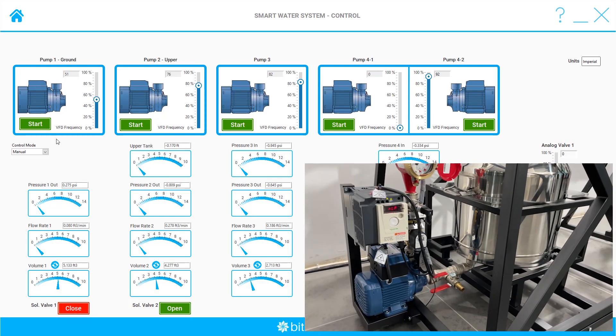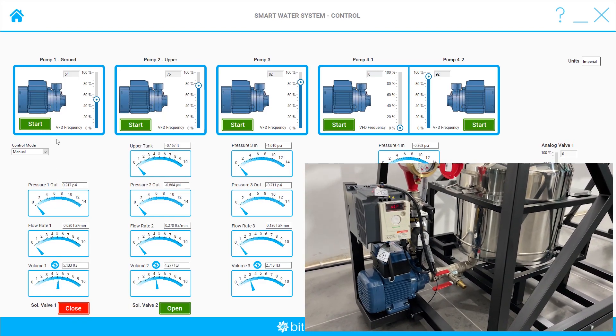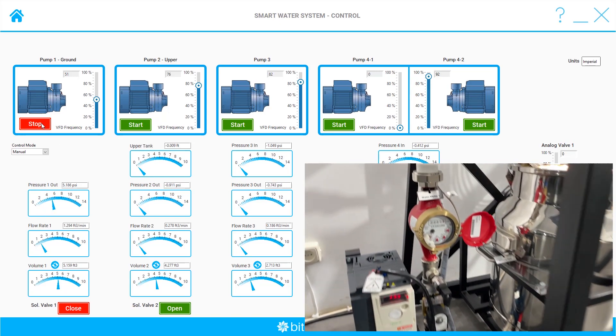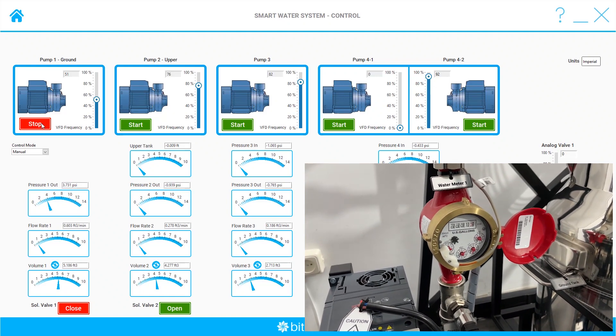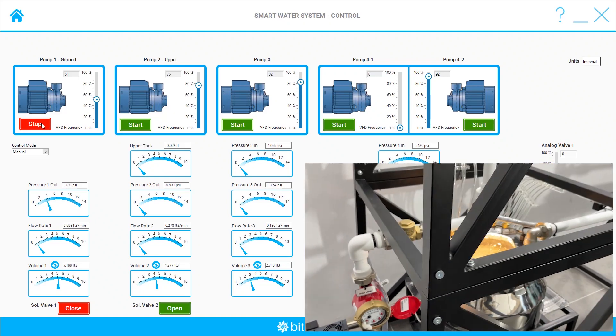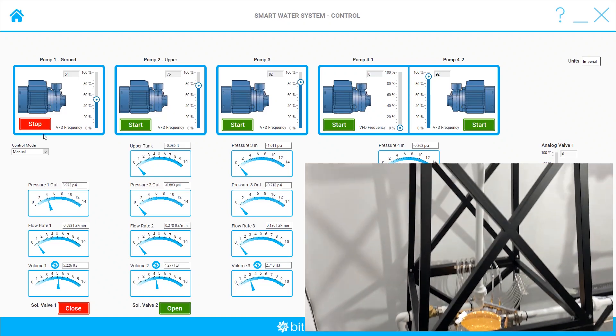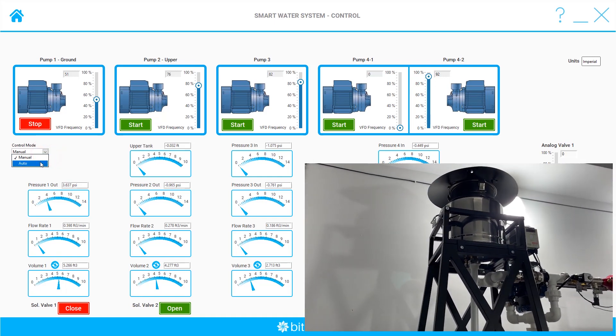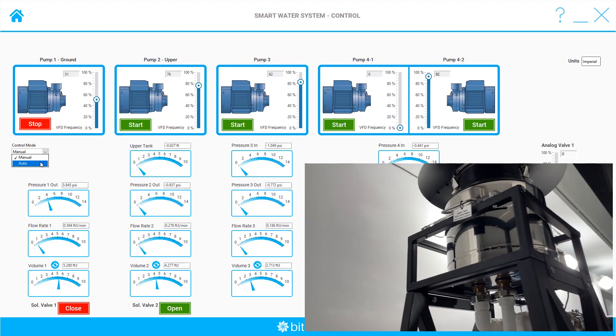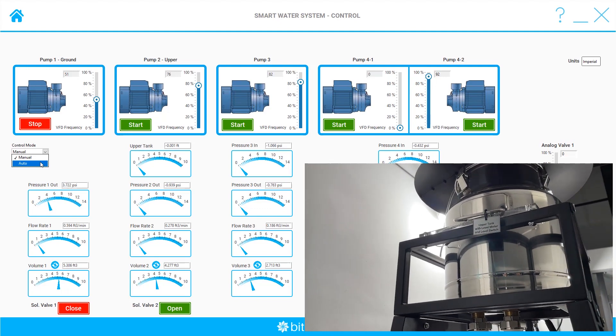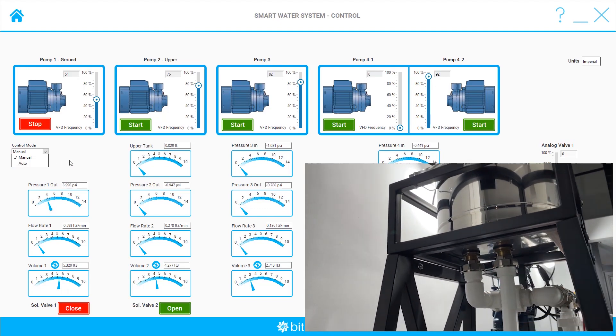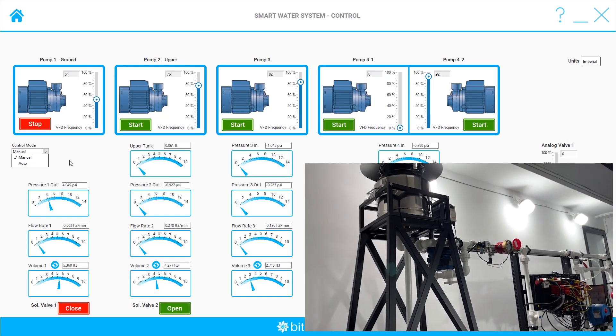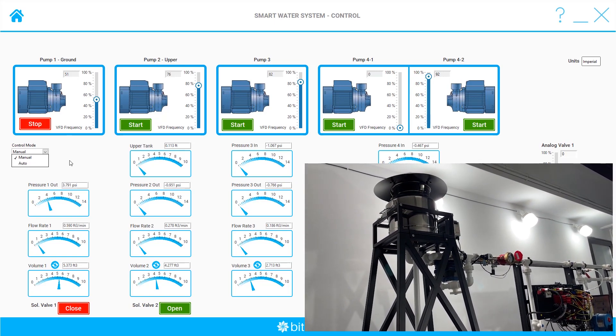Now we can start Pump1 to pump the water to the upper tank. This process has two modes: Manual and Auto. In Manual mode the user controls the pump. In Auto mode the system controls the pump automatically, having the water level signal from the upper tank as a feedback. This way the system adjusts the power of the pump to always have water in the upper tank, regardless of the consumption.